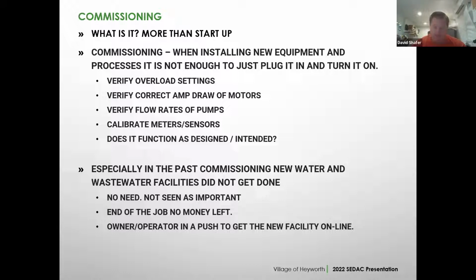But did you check the flow rates on the pumps? Did the impellers get trimmed correctly at the factory? Did they actually ship you what they said they were going to ship you? Were all your sensors and meters calibrated and checked for proper operation? Were valves in the correct position? And then, does it function as it's designed, or as it was intended?